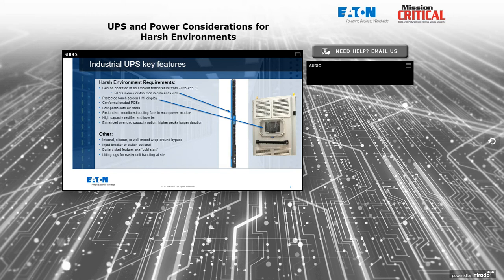Redundant and monitored cooling fans. So the failure of a fan doesn't eliminate the ability to filter the air or cool the UPS. We need redundant fans, and we need to monitor those fans, not just when they stop turning, but when they start to slow down or begin to age. It would be nice to notify the client in advance that I've got a fan that's slowing down and needs attention. Let's do that now before the fan actually stops turning.